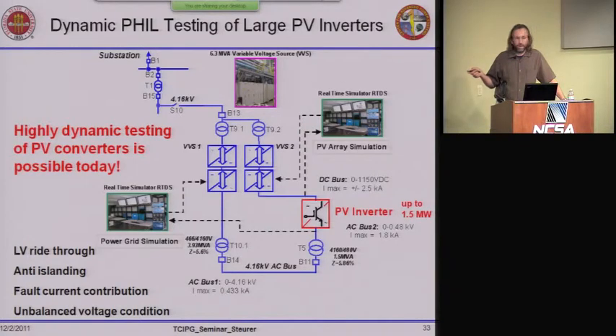On one side, it's connected to the DC bus and receives current from an emulated PV array. On the AC side, it's connected to a simulated rest-of-system, and we impose dynamics and transients on both sides to properly characterize the dynamic and transient behavior of this 500 kW PV inverter, in order to provide a model for more accurate system integration studies. That project is ongoing, and we're now looking at anti-islanding tests and similar studies.